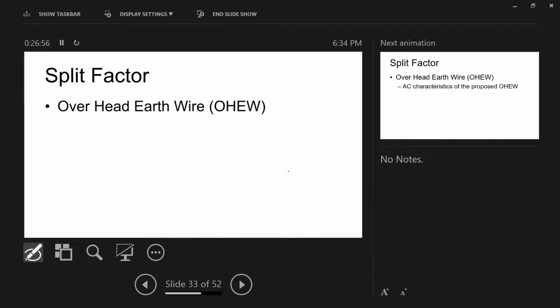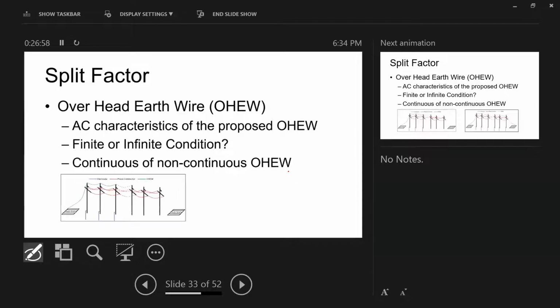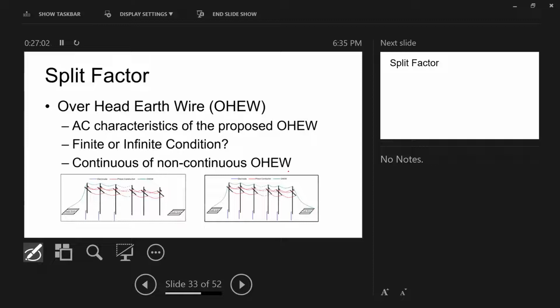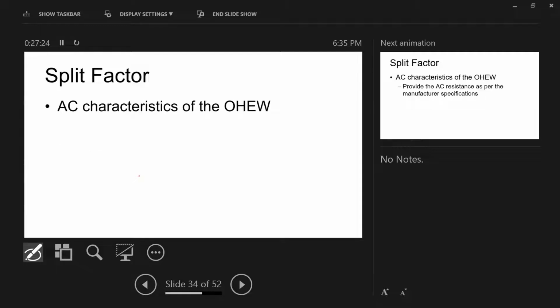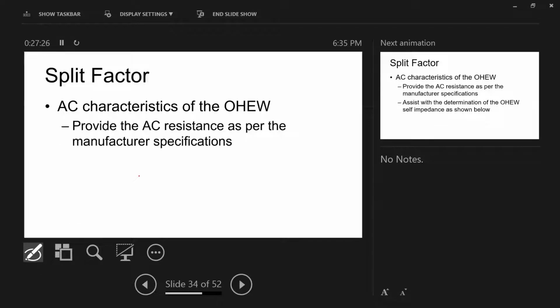So under the split factor, guys, we have to distinguish between two elements. One element is known as continuous overhead earth wire, one element known as broken overhead earth wire. When you have a broken overhead earth wire, it creates a dangerous zone. So we need to make sure that I always have a continuous overhead earth wire between my two substations. You will see what will happen when you go into the system.